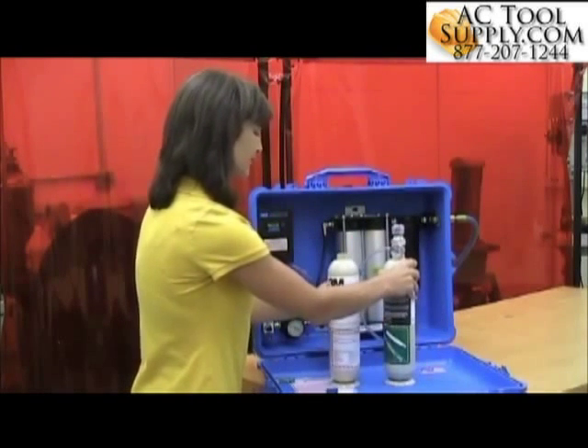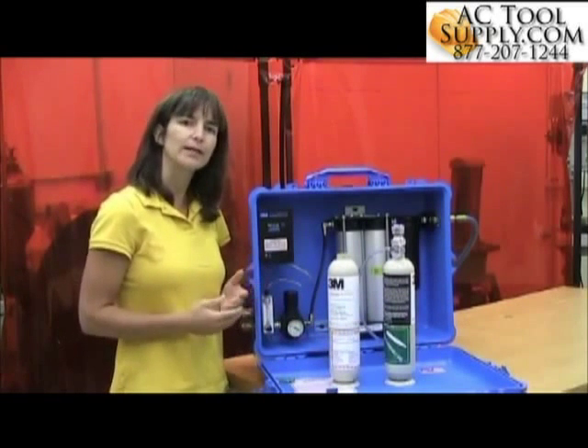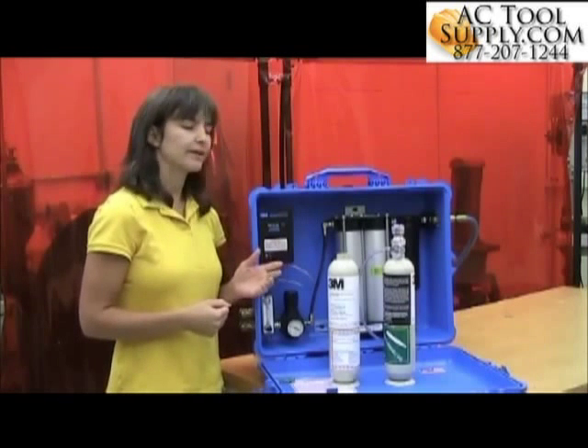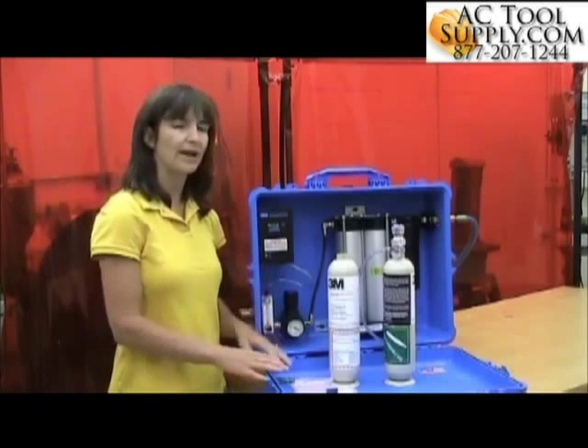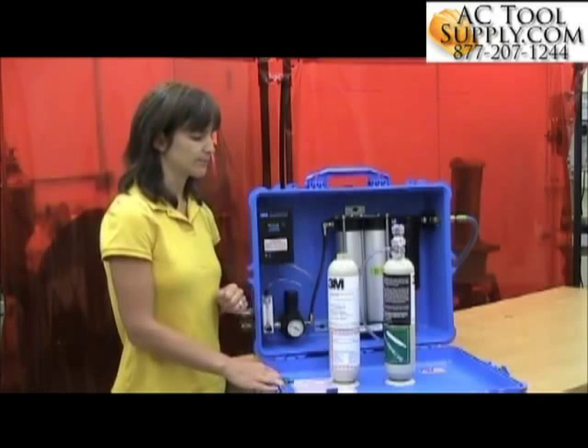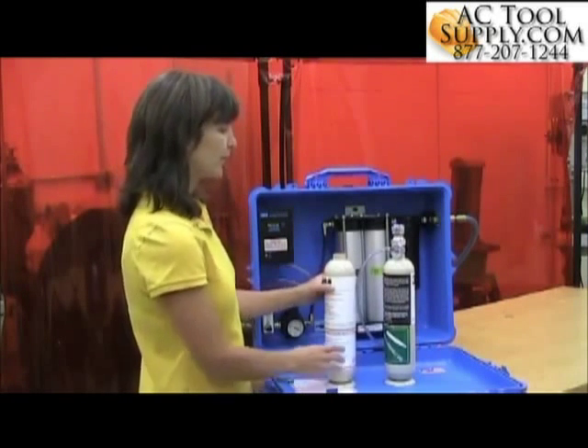For calibration frequency, you're going to want to calibrate every two weeks when the monitor is new for the first month. After that you calibrate monthly, unless you don't use the panel very often — then you're just going to calibrate the monitor prior to each use.